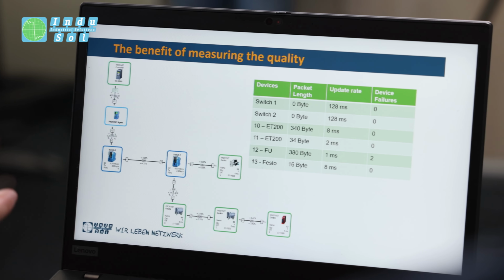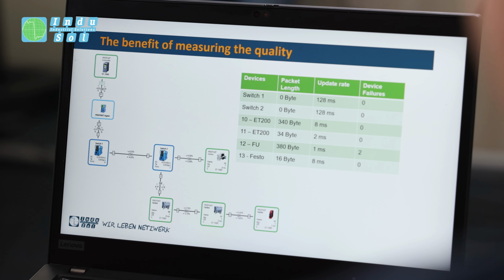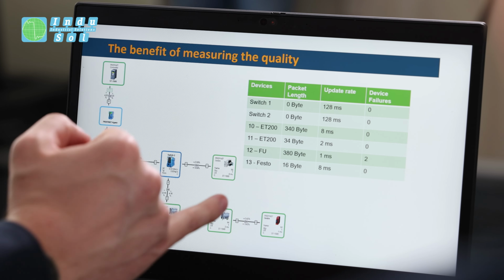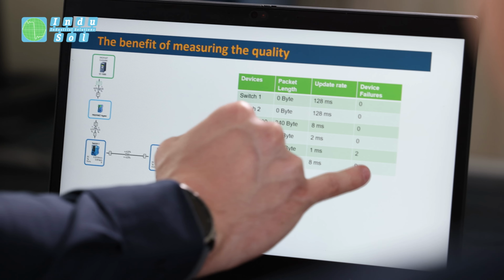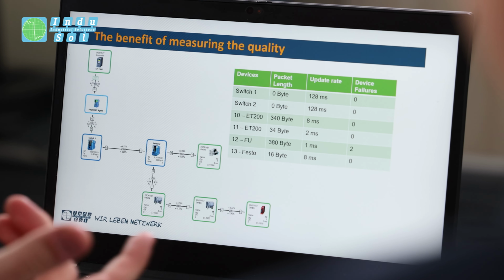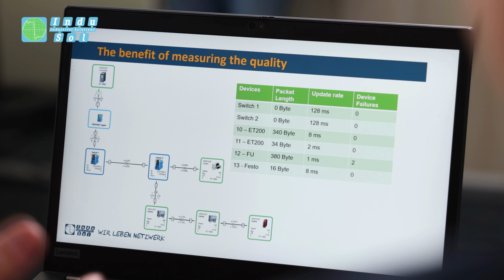Exactly, and also for troubleshooting it's easier. I have an example for you. You see a network structure, a very easy network structure. The situation is that your device number 12, the last one, over the day had two failures. The operator had to acknowledge the error and could restart the machine, and it was working. Then sporadically again an error, same device. That's the situation.